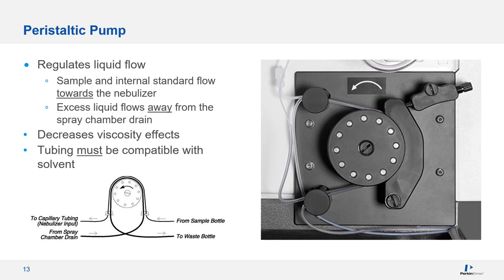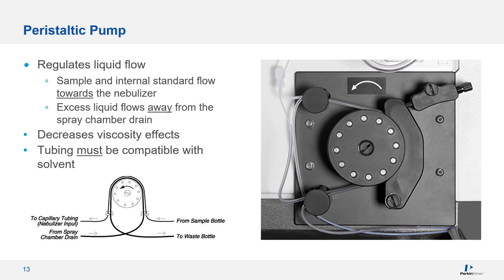First, you need to choose the right tubing type for your matrix. I'm talking about the peristaltic pump tubing here. Most labs use PVC, but depending on the solvent you use, solvent flex, silicone, or viton might actually be more appropriate. It's always a good idea to verify the solvent compatibility of materials if you aren't sure.